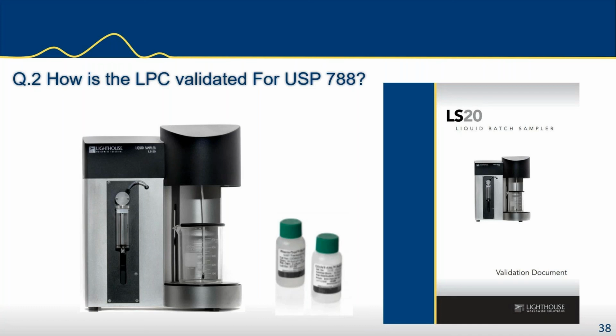They're called count cal. And as I said, they usually have a concentration of 3,000 particles per milliliter, plus or minus 10%. So the verification of the validation is acknowledged when the liquid particle counter passes the count ratio test using these 15 micron particulates. And the corresponding counts should fall within 2,700 and 3,300 particles. That's at 10%.